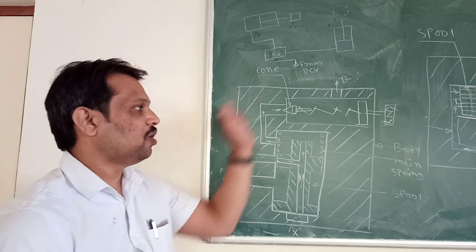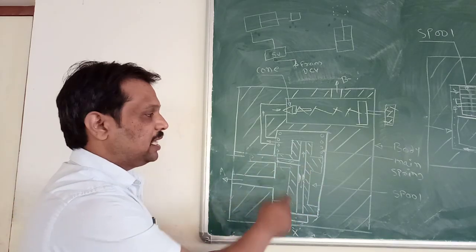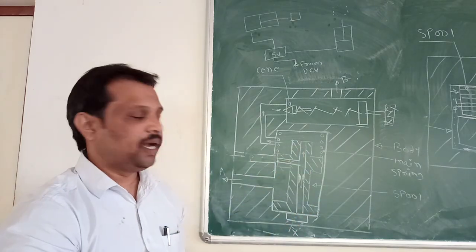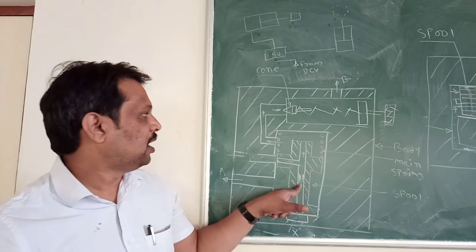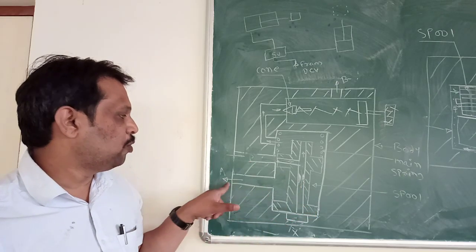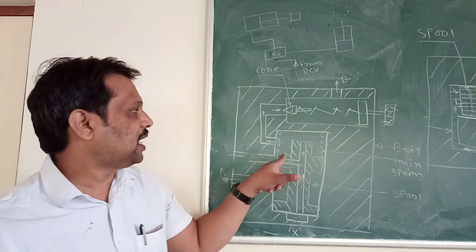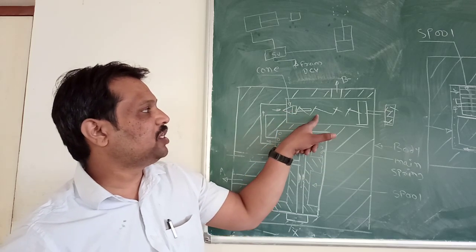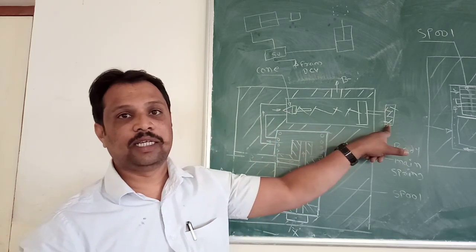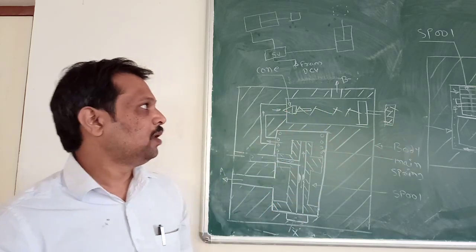This is your valve body. In this valve body, this is the spool. In this spool, there is a passage provided, and in this passage there is an orifice. After that, port P is there, port A, and port B. This is the main spring. This is the conical element on which the spring is mounted, and this is the adjusting screw for the pressure setting adjustment.